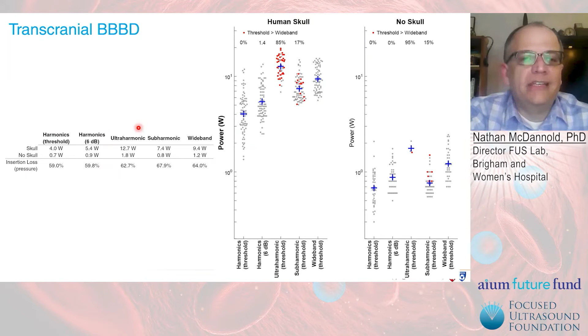And then comparing these thresholds with the skull and without the skull. Again, these are early studies with 1 skull and just a couple of experiments, but we can get an idea of what the attenuation is. So it's around 60% if you compare the threshold. This is the insertion loss in pressure amplitude. So you can see that there is still significant loss, even though we're at a very low frequency with the 230 kilohertz of the low frequency Exablate system.